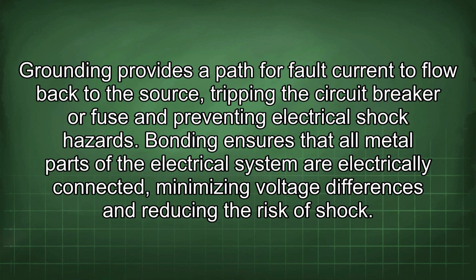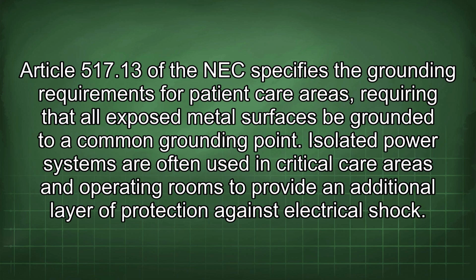Grounding provides a path for fault current to flow back to the source, tripping the circuit breaker or fuse and preventing electrical shock hazards. Bonding ensures that all metal parts of the electrical system are electrically connected, minimizing voltage differences and reducing the risk of shock. Article 517.13 of the NEC specifies the grounding requirements for patient care areas, requiring that all exposed metal surfaces be grounded to a common grounding point.